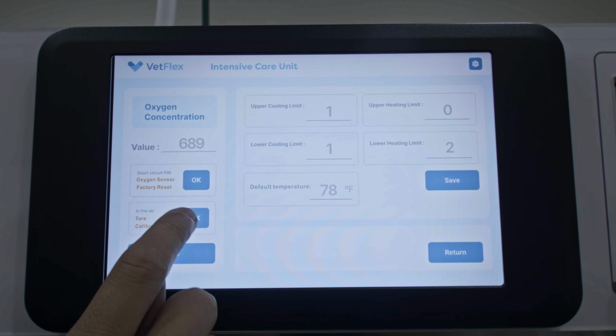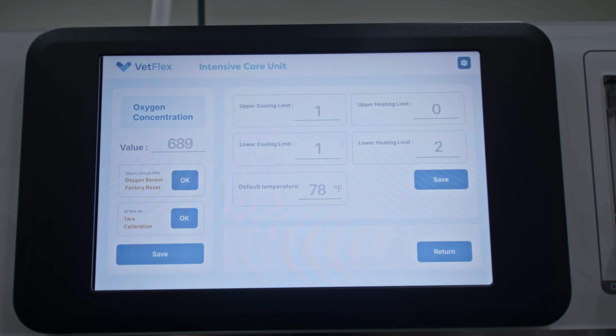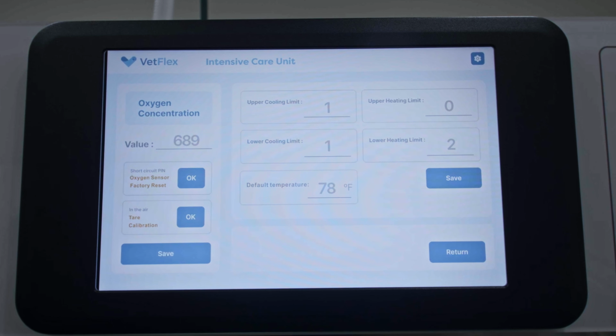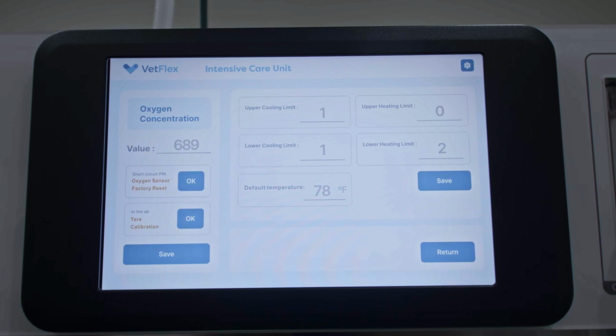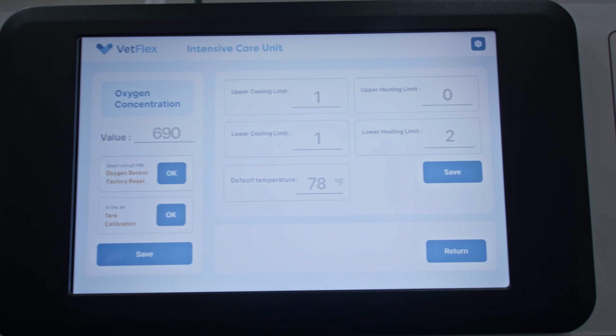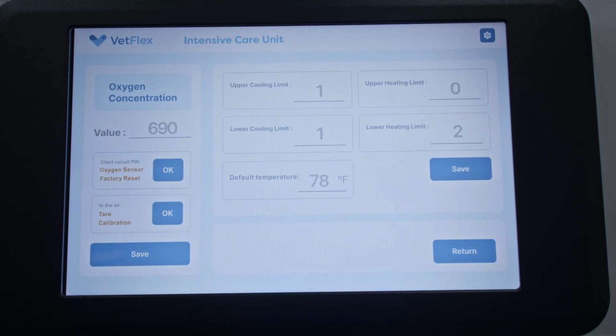Let the sensors stabilize and wait for the oxygen concentration value to become stable on the control panel, then hit OK next to tare calibration, then save and return to exit settings.